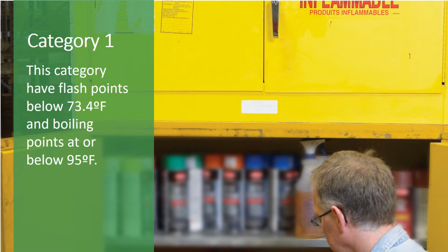OSHA classifies flammable liquids in four categories. In this section, we will touch on the four categories and flash points, along with looking at an example of each liquid. Category 1 flammable liquids have flash points below 73.4 degrees Fahrenheit and boiling points at or below 95 degrees Fahrenheit. An example of this type of liquid is liquid propane or butane.